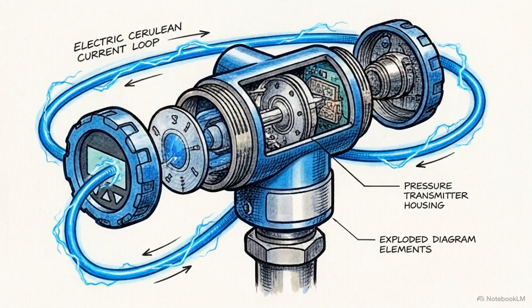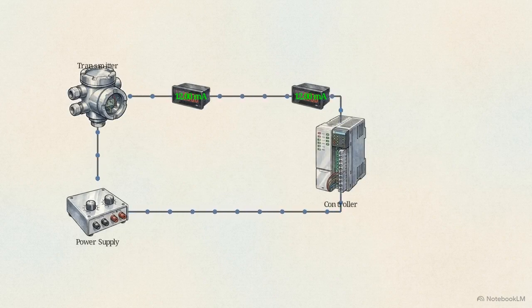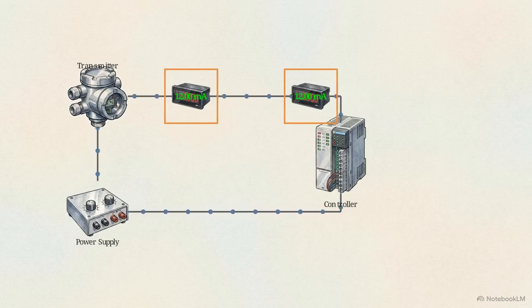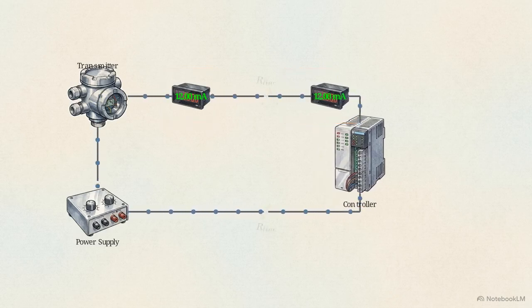To solve this, process engineers rely on the 4 to 20 milliamp current loop. This method leverages a basic axiom of circuit design. In a closed series circuit, the electrical current is exactly the same at every single point. The transmitter is an active regulator, pushing electrons at a precise rate. The source and receiver ammeters read the exact same value.